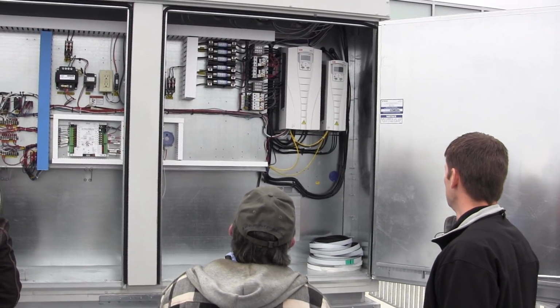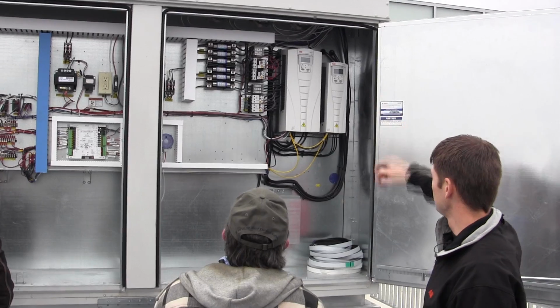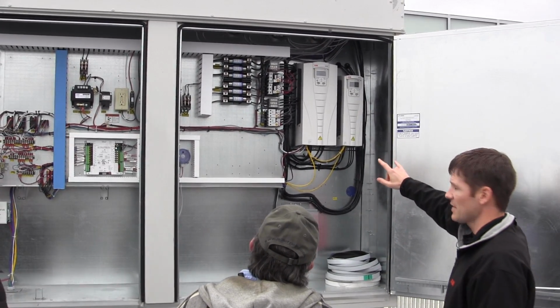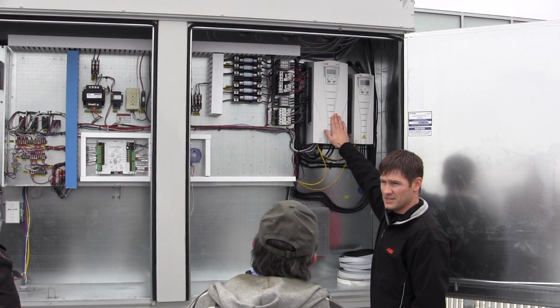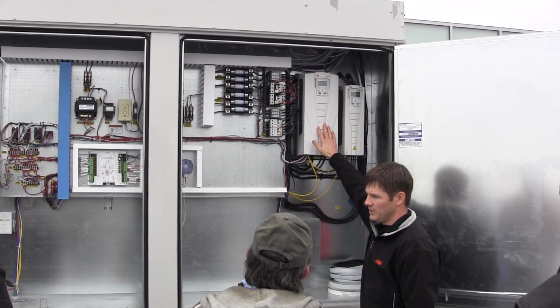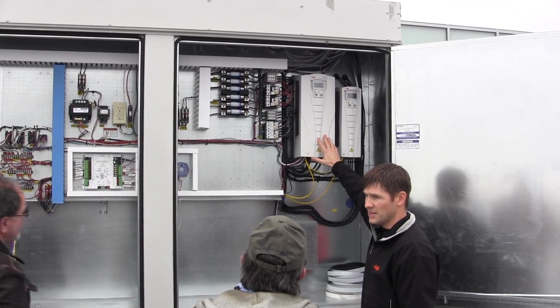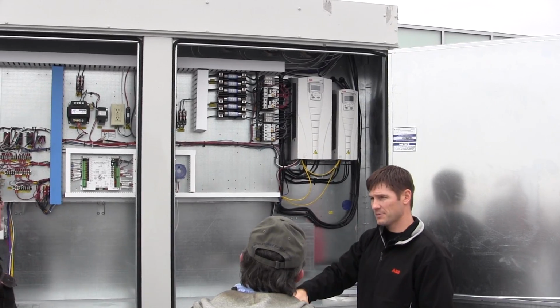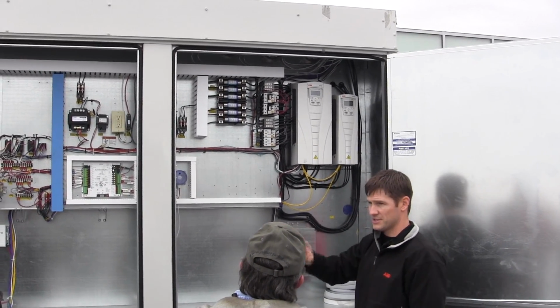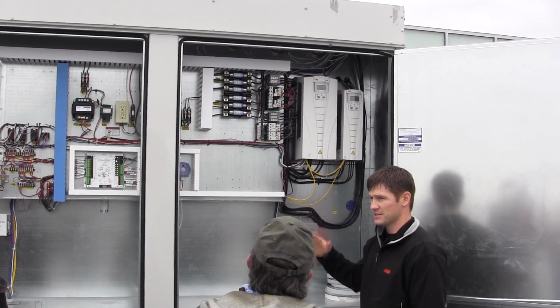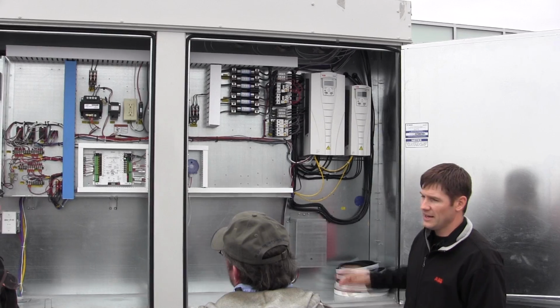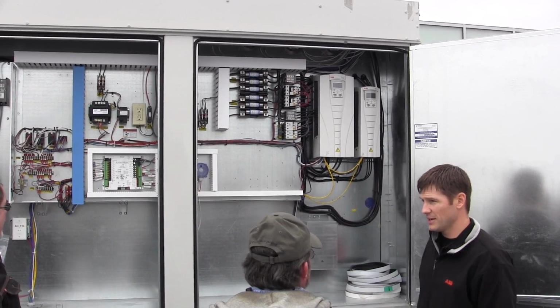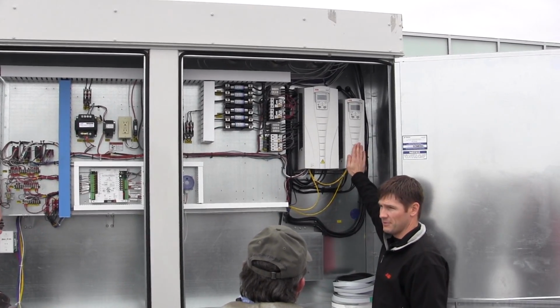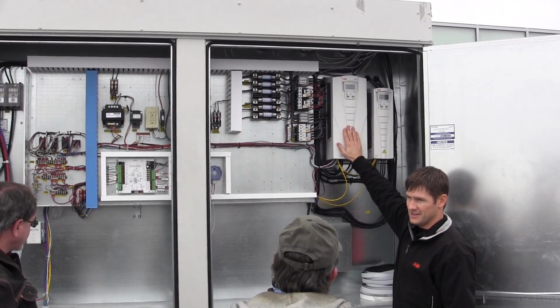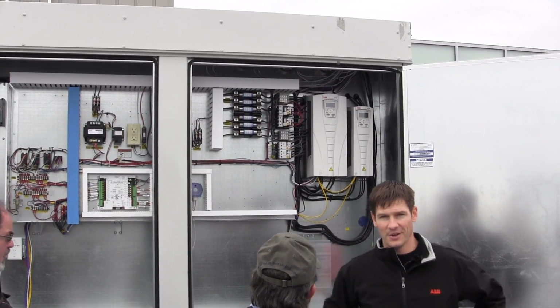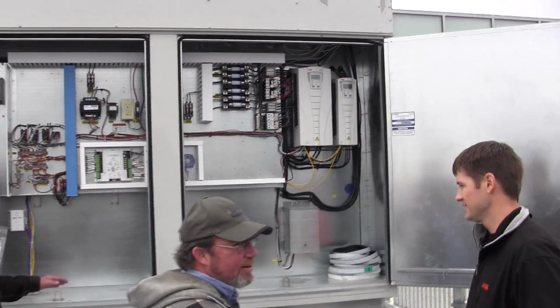And that's a filter static? Yeah, up there, filtered. And right now, we discovered this last time, you can see this is only running at 26 Hertz. That's 26 out of 60. So it's creeping along, and we looked at the graphics and it's doing what it's supposed to. The sequence controls the supply fan to maintain a duct static pressure, and then it controls the exhaust airflow to match the supply airflow. Right now there are rooms that aren't exhausting quite enough, because this exhaust fan is being held back from running full speed since it matches the supply. That would be a building pressure issue, and I don't know how to get around that. We were talking about that last time.